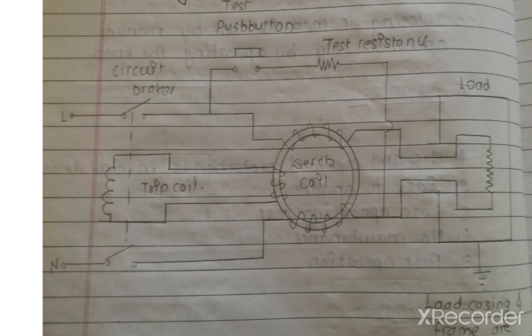While talking about the working, in normal operating condition, the phase current and neutral current in these two wires are the same. Due to this, the flux produced by these two wires is also the same. But the direction of this flux is opposite to each other. Due to this, the net flux in this core will be 0. If there is an earth fault on the device, then a leakage current flows from the phase to the earth directly. Due to this, the phase current is higher than the neutral current. Therefore, due to the difference in these two currents, that is live current and neutral current, an EMF is induced in this coil, which is the search coil. Due to this, the relay operates and the contacts are opened.